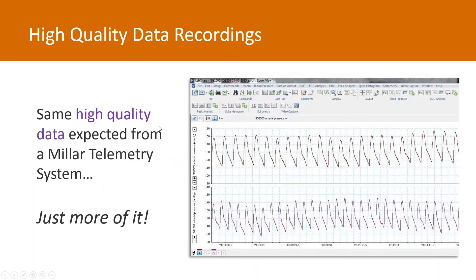Are there any effects on the quality of data received? This is a representative screenshot of arterial pressure obtained from two cohoused rats. On a beat-to-beat basis, there is no impact on data quality. Over a 24-hour period, there is no difference in quality or quantity of data received when animals are cohoused compared to housed separately. With cohousing, you still get the same high-quality data expected from a Millar telemetry system, while also being able to collect more data from the same rat through dual telemetry implantation.